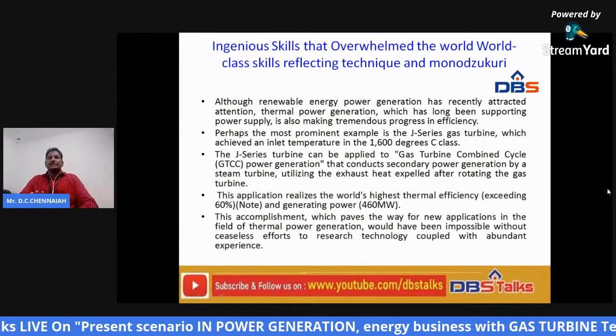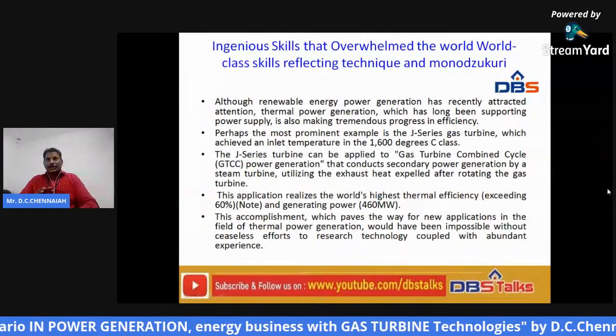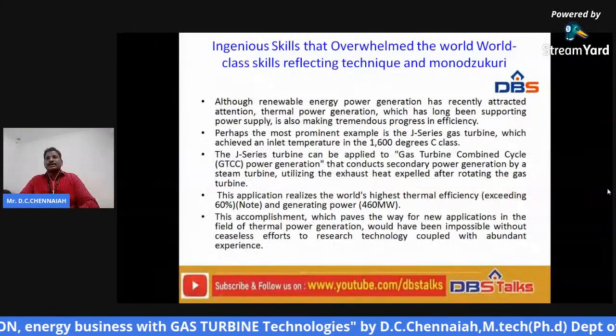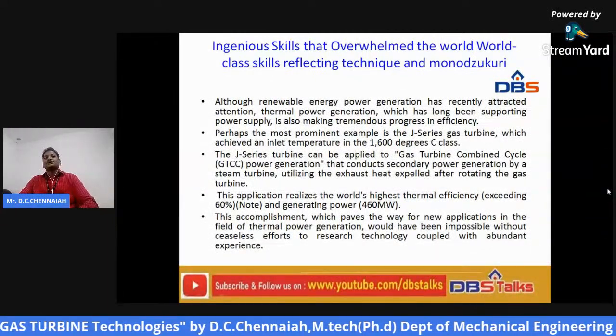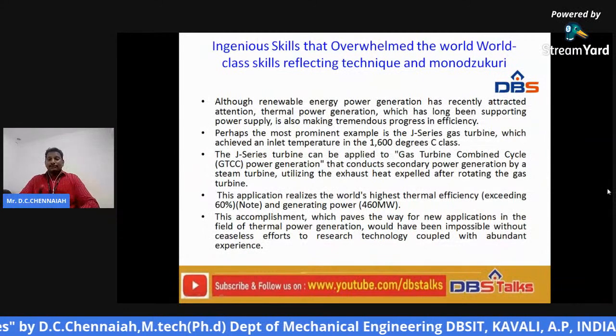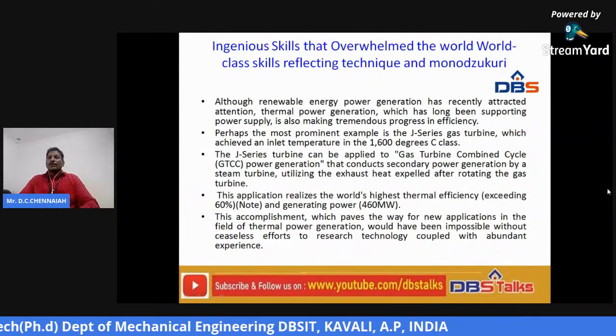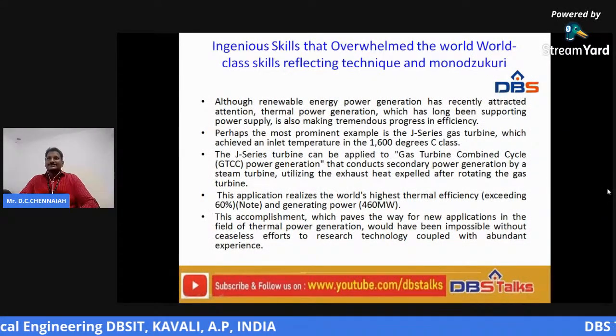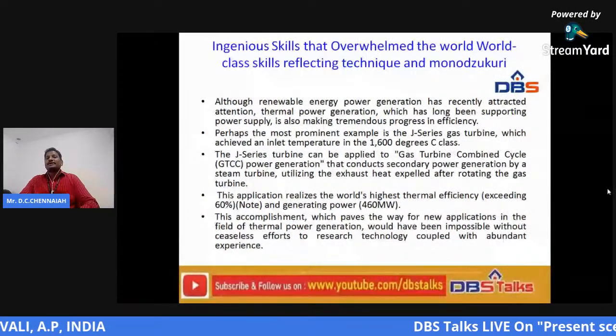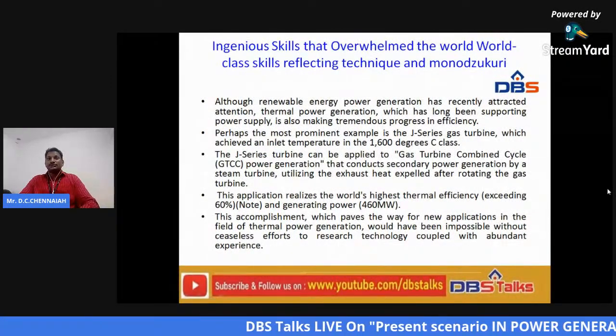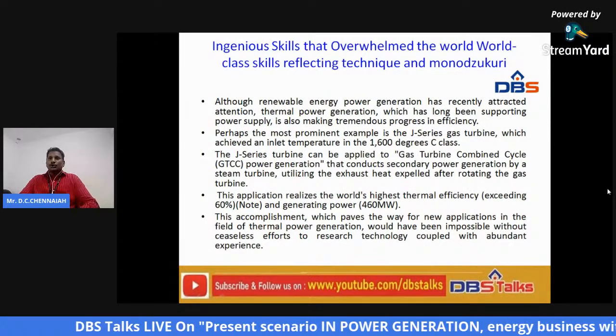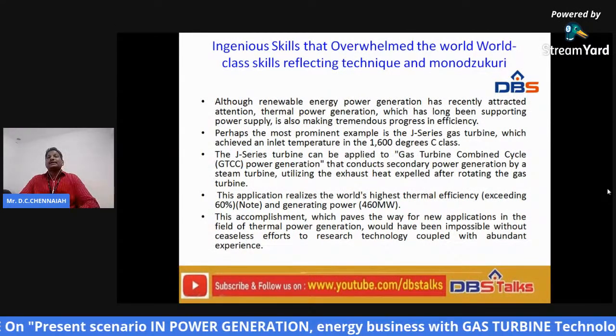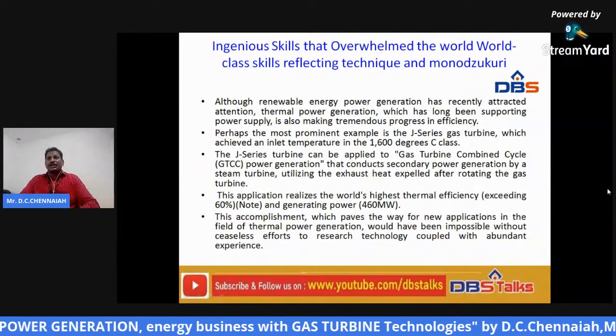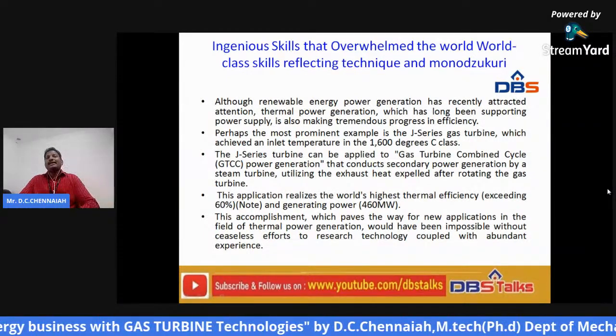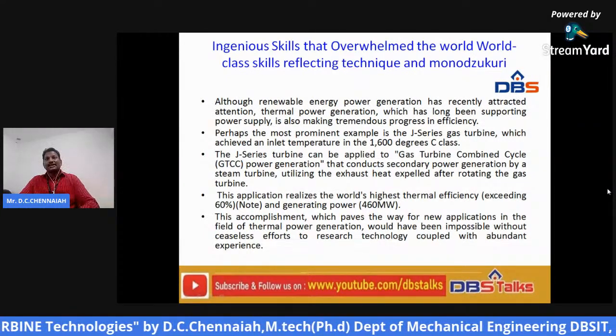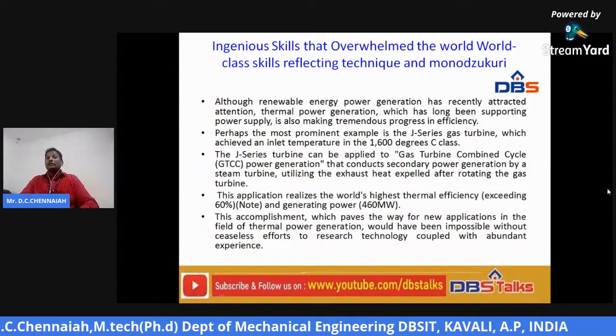For that we supply the fuel, but the same generated heat is used in the secondary cycle also. That is why we get power output: the first power output from the gas turbine, and the second power output from the steam turbine. So thermal efficiency equals total power output divided by supplied heat, and the supplied heat is the same. That is why we get higher thermal efficiency and generate power of 460 megawatts.